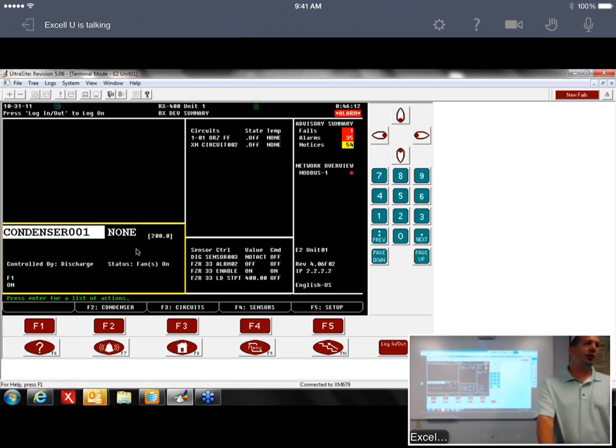So when they came out with CC100, they put it on the Echelon network. At that time, Echelon was popular and a lot of people were using it, so that's why they adopted it. Well, that's pretty much gone away now. We learned a lot of lessons about Echelon, I'm not a big fan of it, it's a very complicated network. So when we came out with this one, it works on a Modbus network. So here we are, third case controller, third different type of network. But the Modbus network is very similar to an I/O net, it uses the same cable.